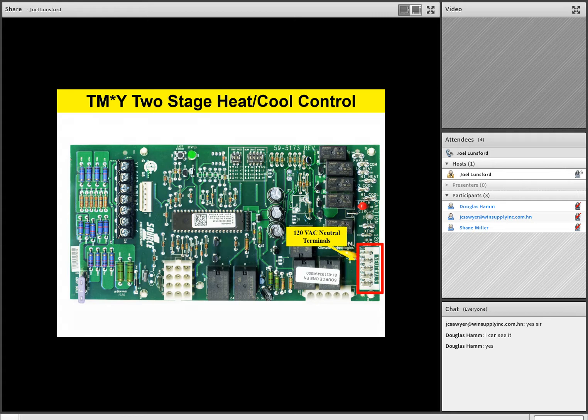As we move around the bottom of the board, we see we have an output harness to our hot surface igniter and our inducer fan motor. Should be noted those are line voltage components. As we come around the board, we have our 12-pin harness with our 24 volt inputs and outputs to our gas valve and our safety circuits and our pressure switch and so forth. We have a 3 amp fuse on board, and if you look closely on the left-hand side of that fuse, you'll notice that 5 amp maximum. And so we ship it with a 3 amp fuse, but the technician, if they need to, can go to a little larger fuse if they need to.